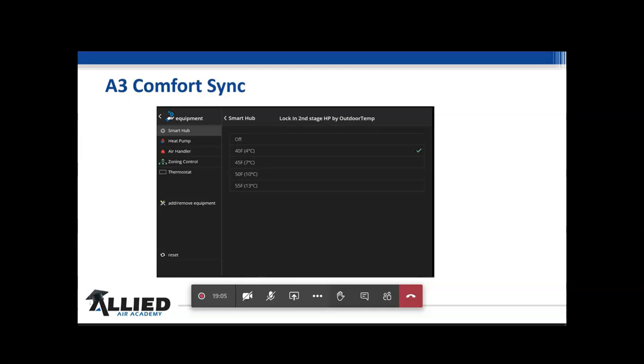If it's running at lower stage, it's going to run a long time, and our cumulative runtime will build up in that case. But if we don't run and we go full stage, 100% capacity, we might not run as much. So there's a fine balance in there that you're going to have to look at for your particular region and where you're at. If you're in the panhandle of Florida, it's going to be much different than if you're in the Tennessee Valley. Completely different set of circumstances, completely different set of settings right here. But this is where it is on the equipment, on the A3 comfort sync.